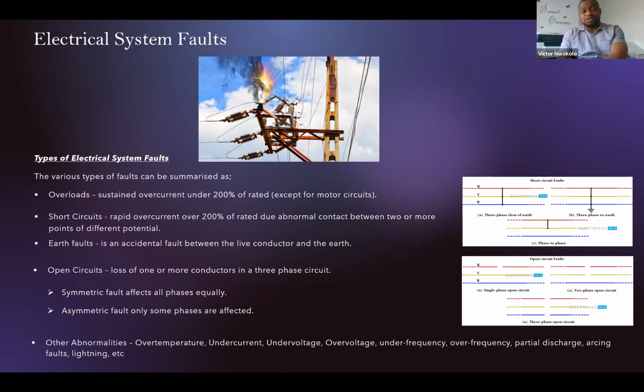We also have earth fault. Earth fault, or ground fault in America, is another type of short circuit. But in this case, the short circuit also extends to ground. And where you've got a short circuit that makes contact to ground, we call that earth fault. And the reason why I separate them is because we protect against them differently. We protect against the normal short circuit between phases differently from how we would protect against the earth fault in an electrical system.